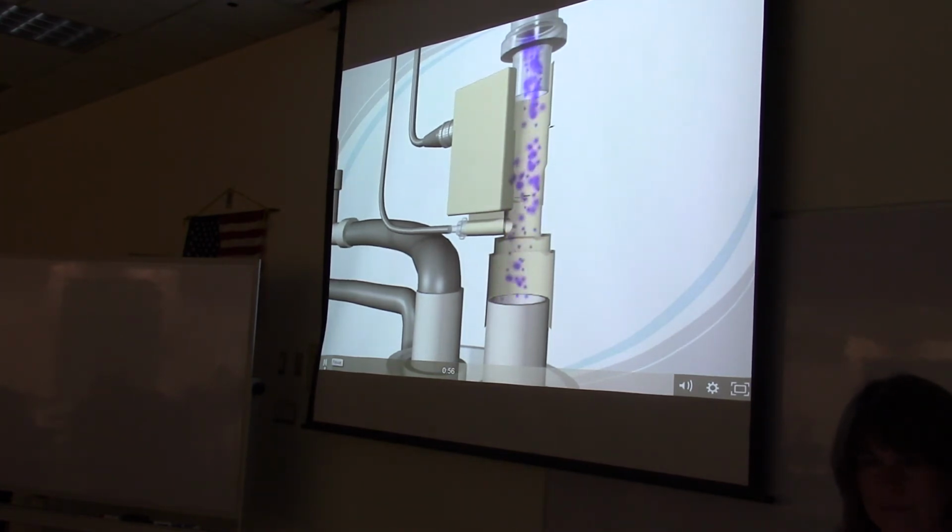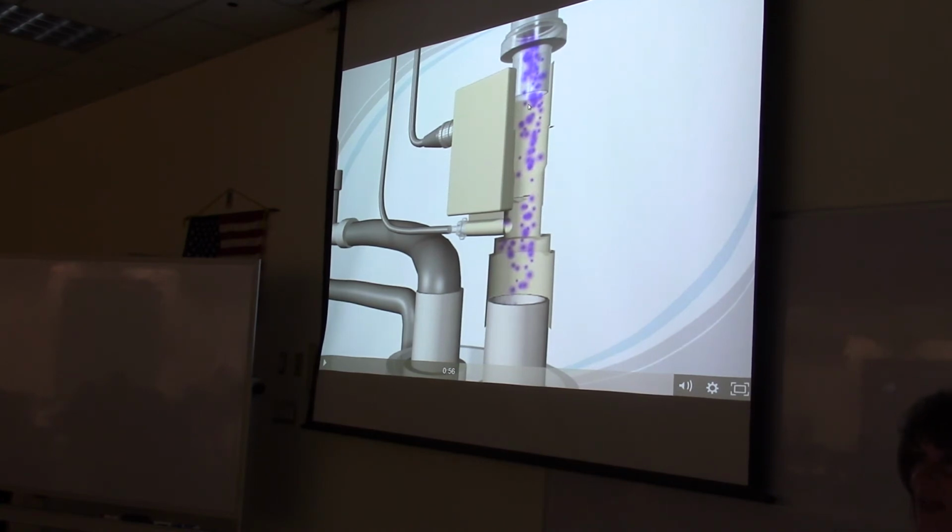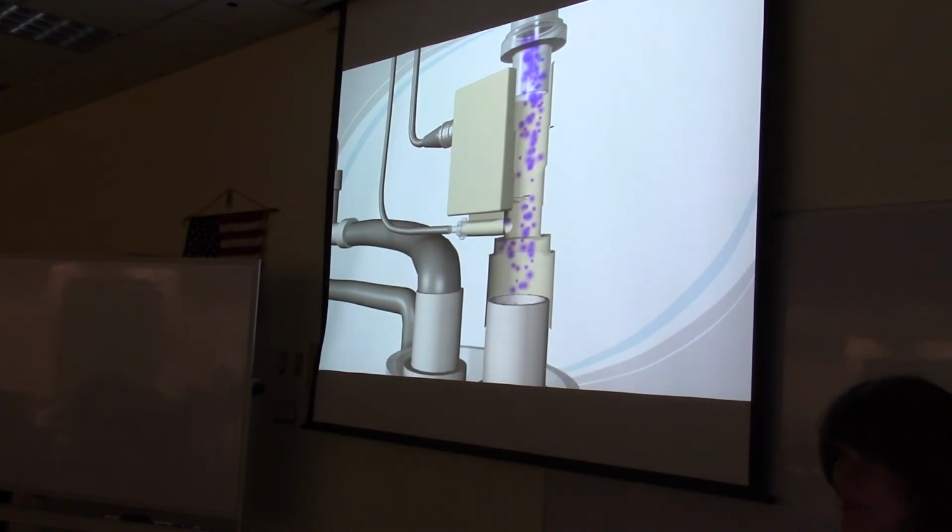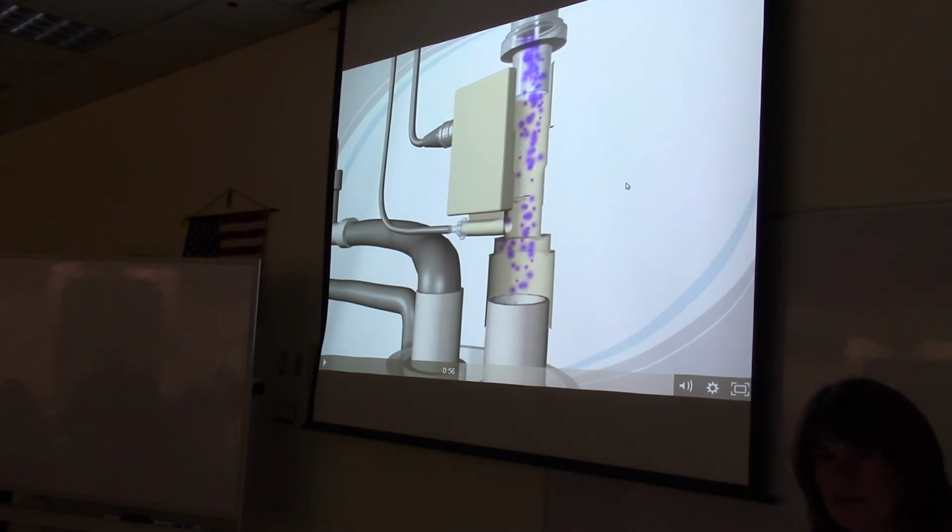I don't know if you can hear that. No. Okay, so it's just telling you that you've got the injector module on the dry side of the humidifier, and you can tell that this tubing and this sensor is monitoring the flow of gas and determining several times a second how to adjust the amount of nitric oxide flowing in based on the flow. So it's just a highly efficient device at looking at the flow and knowing how much to inject into it.